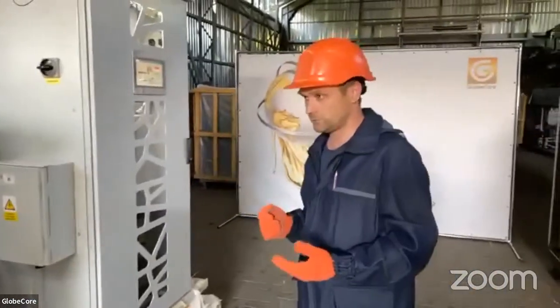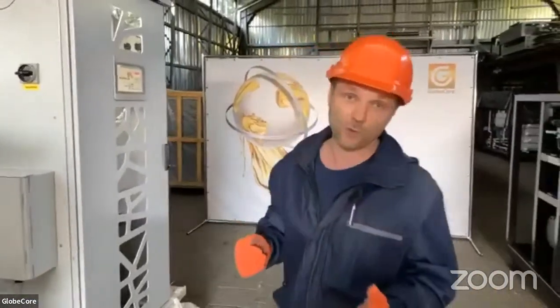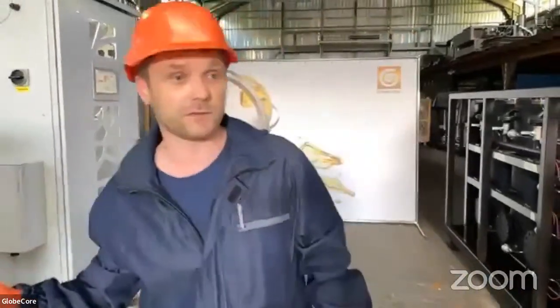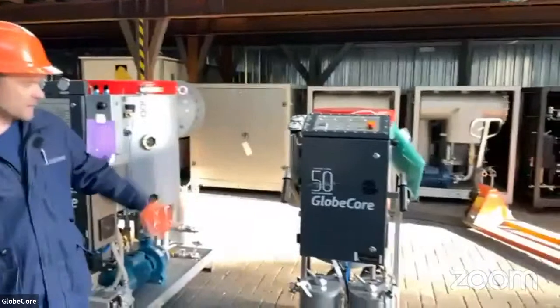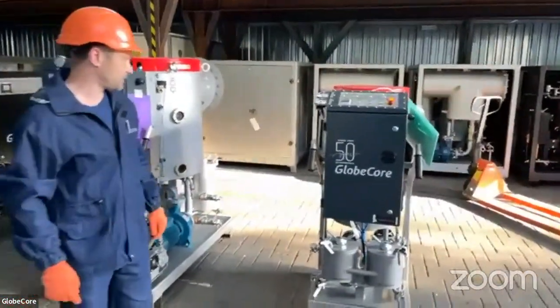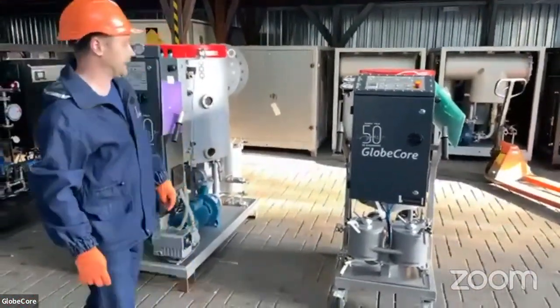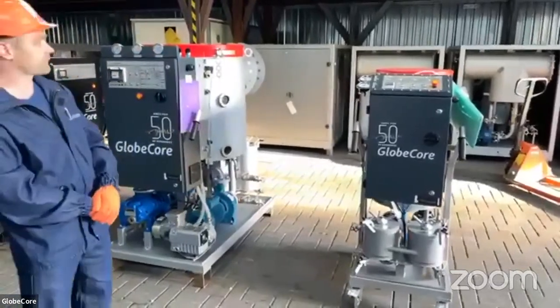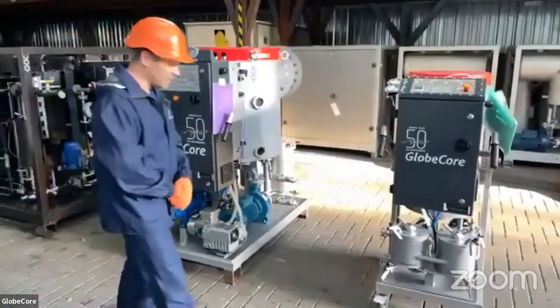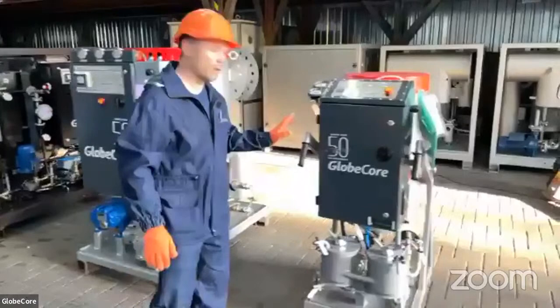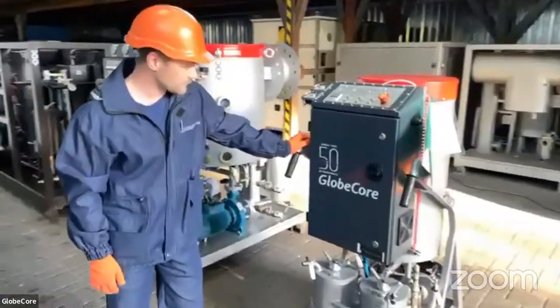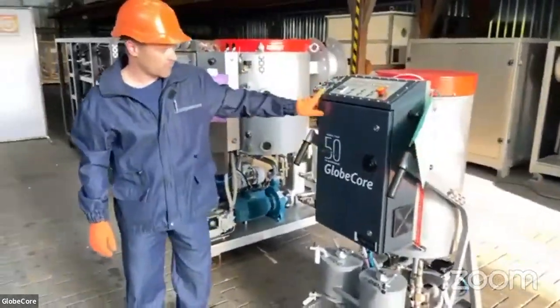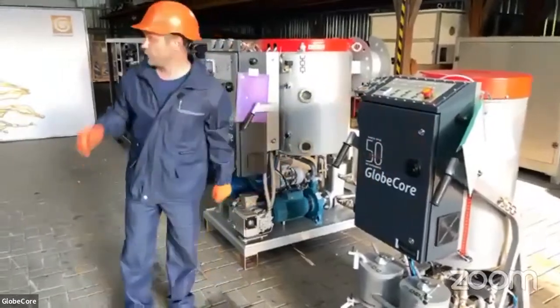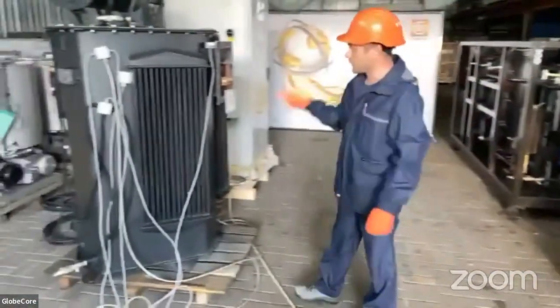And to remove water from the transformer as a whole, we use the drying unit. This is the simplest unit in the GlobeCore product line. It has the capacity of 400 liters per hour. And with this unit, we treated this transformer.